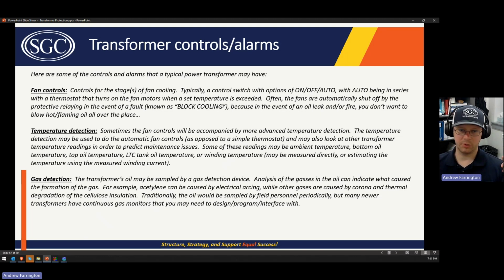You almost always include some sort of block cooling in your transformer protection if your transformer is big enough to have its own automated controls. The reason for that is if there is a transformer fault and the transformer catches on fire, obviously that's going to heat up the transformer and you don't want your fans kicking on and blowing air to the fire, or worse yet, there's a rupture in the transformer and it's spewing flaming oil and your fans are just blowing it all over the substation. That's really bad. So usually you have block cooling that's executed by the transformer lockout relay.